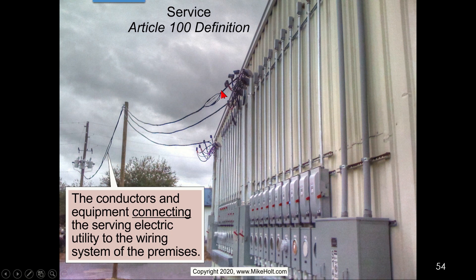Our wiring comes in, and this is the equipment — this is the service equipment — this is our whole service right here. The service equipment ends at the main means of cutoff. You can see the main means right here — those two big disconnects right there. So you have service from the utility, the two main disconnects, and that is the service equipment.